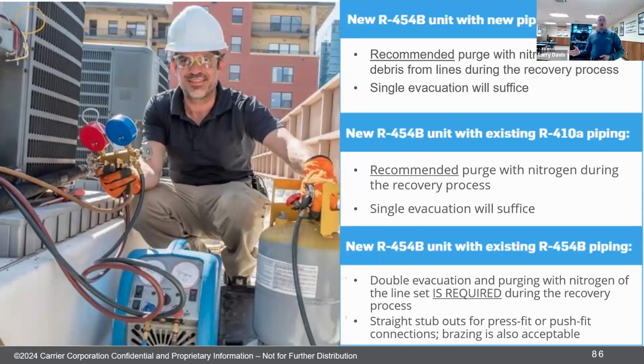You evacuate, you recover the refrigerant, you evacuate the system to, I think it's 1,000 or 1,500 microns. You break that vacuum with nitrogen, then you evacuate it again down to, I think, 500 microns, bring it up to 0 PSI with nitrogen, then you can open it up. So we'll talk about that process here pretty soon.